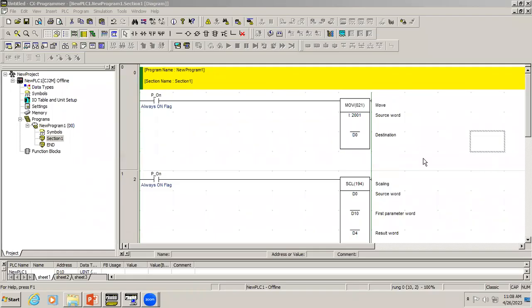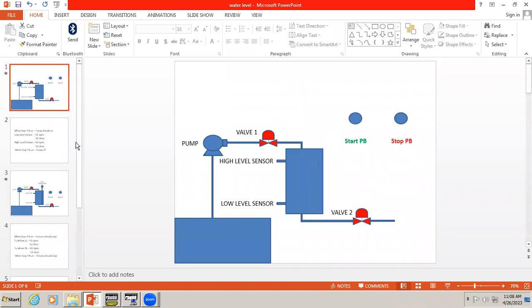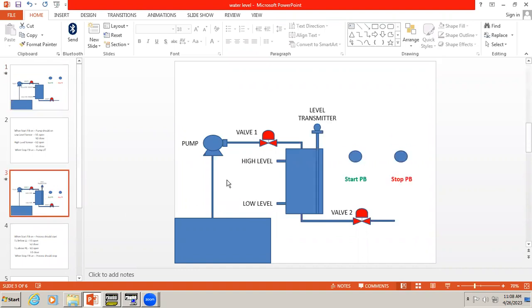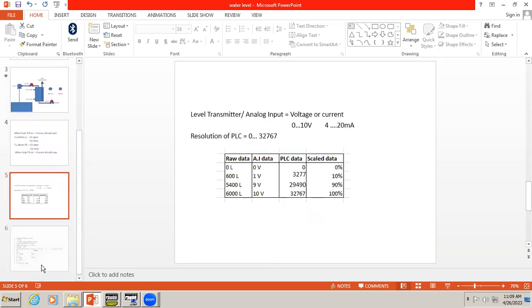Welcome to automation training. In the last video we have seen how to use analog signals. Before that we did one example of tank level control. In that program we were using a level switch, but now instead of a level switch we'll assume we have a level transmitter which is going to give the tank level continuously. In this case we have a low and high level — low level is 600 liters and high level is 5400 liters — and we want to maintain the tank level within this range, so we have to develop the program.